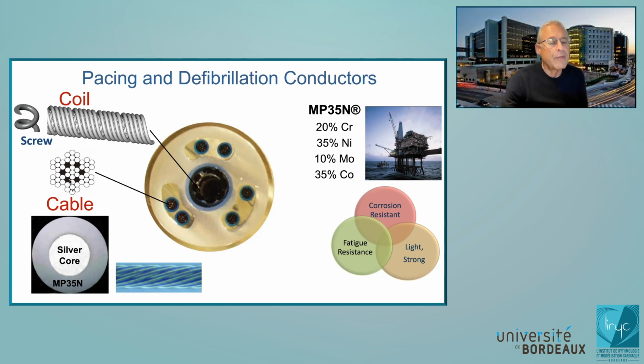To allow very high power signals to go through to the heart without using up too much of that energy as heat in the lead, all defibrillation leads have a certain number of filars that are made out of silver. So they typically will have a silver core, a very low resistance conductor. Platinum has also been used inside a MP35N shell.